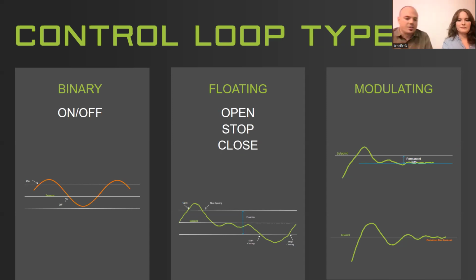So a floating actuator is going to be using a combination of timing and open and closed signals, which are two distinct binary outputs. There's a binary output associated with your open command, and a binary output associated with your close command. Let's take, for example, that chill water valve we saw in our earlier example. If this had a floating style actuator, it would have the correlating open signal and closed signal. You would also see that this particular actuator has a 90-second drive time. That means that if it's completely closed and I want to go fully open, it's going to take 90 seconds or thereabouts to get there.